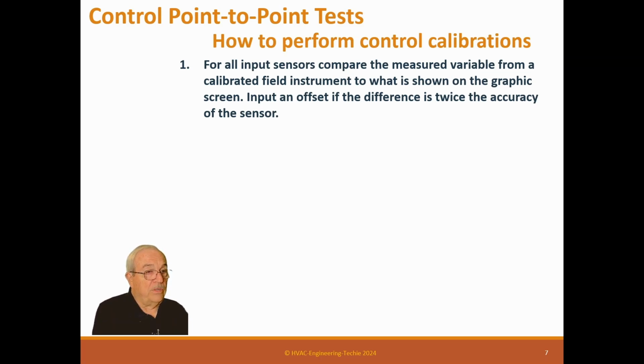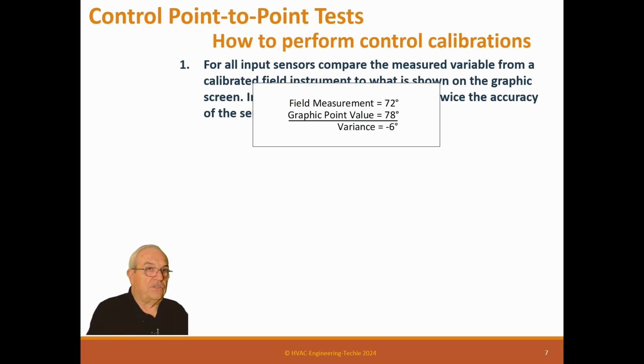And it depends on what point that is. If it's a general point, not really important, I wouldn't do that. If it's really, really important, maybe you would do it. So there is that condition. Now here's a condition. So your field measurement was 72 degrees and the graphic point showed 78 degrees. So you subtract the two and the variance is a -6. Okay. The sign is really, really important because if you get the sign wrong, that's twice out of calibration.